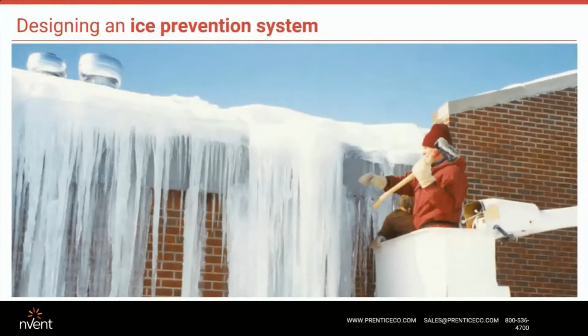We run the heat trace cable right on the roof, as you see on the left-hand side of the picture, zigzagging it across. Its purpose is to keep water moving, so you want to keep the heat trace not only on the roofline but in the gutters and downspouts, all the way down to the surface where it either refreezes safely or goes into an underground sanitary system. That's very important.